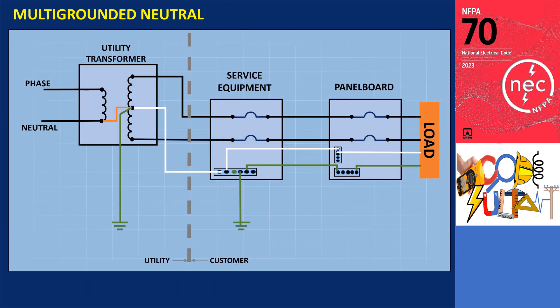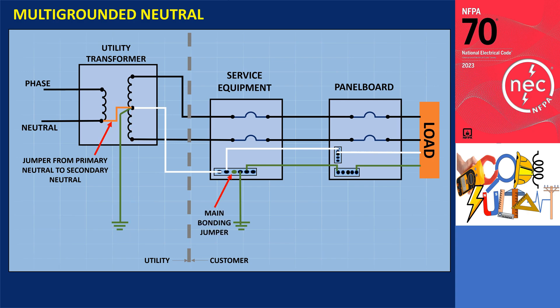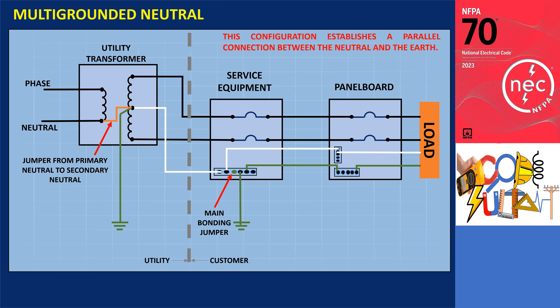The illustration depicts a utility transformer where the primary neutral is bonded to the secondary neutral, and both are connected to the earth. On the customer side, it is necessary to bond the neutral to the grounding electrode at the service equipment or disconnect. Consequently, the secondary neutral is connected for the second time, resulting in a parallel connection between the neutral and the earth. When the primary current leaves the transformer winding, it undergoes division. One path leads back to the substation through the multi-grounded neutral conductor. The neutral current flows through the bonding between the primary and secondary neutral conductors, establishing a parallel connection between the neutral and the earth, enabling electric current to continuously flow into the earth.